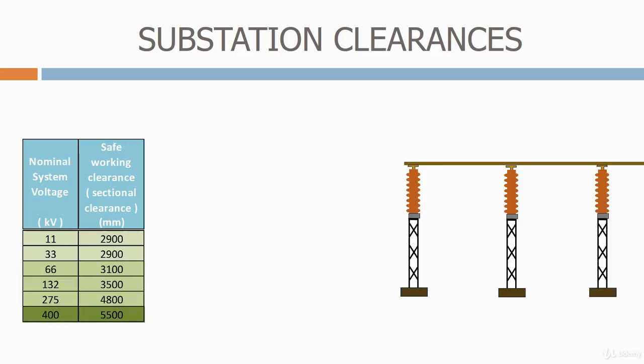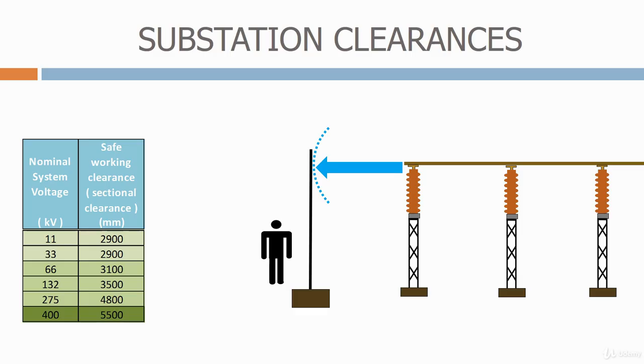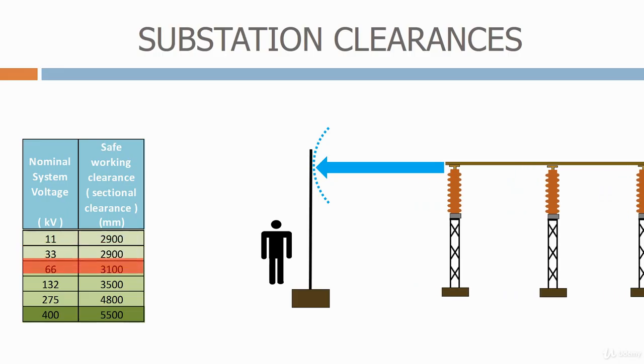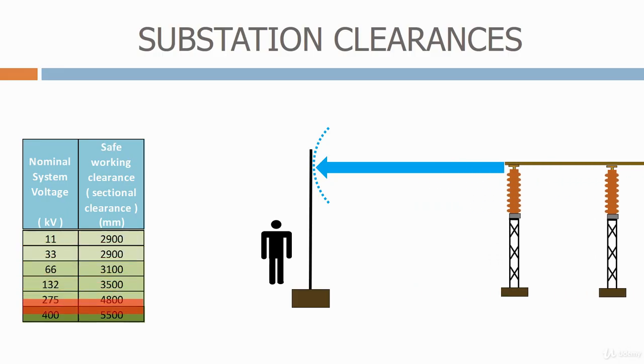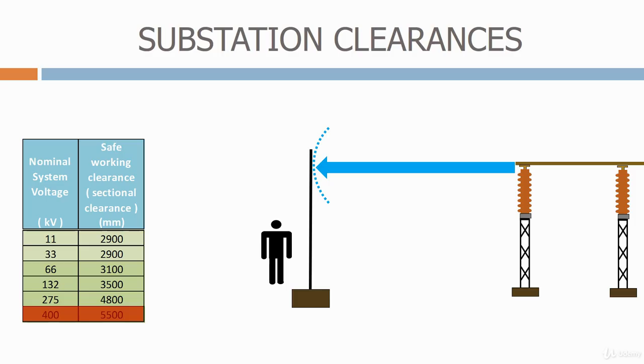Here we have a bus bar supported by some post insulators. Most substations have a security fence around the perimeter. It's obviously important that members of the public stood outside the perimeter fence are safe. We therefore need to make sure that the perimeter fence is a defined distance away from live conductors. For 11 kV, the safe working clearance, or sectional clearance, means that the perimeter fence must be at least 2.9 meters away from the nearest live conductor. For 400 kV, the fence needs to be at least 5.5 meters away.